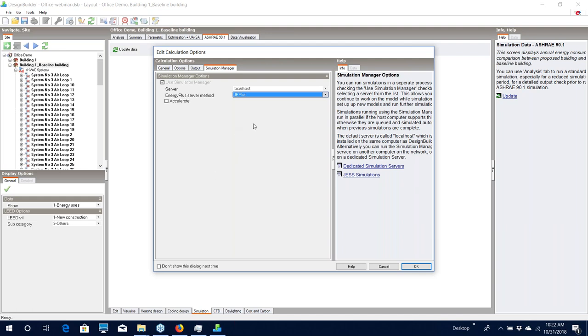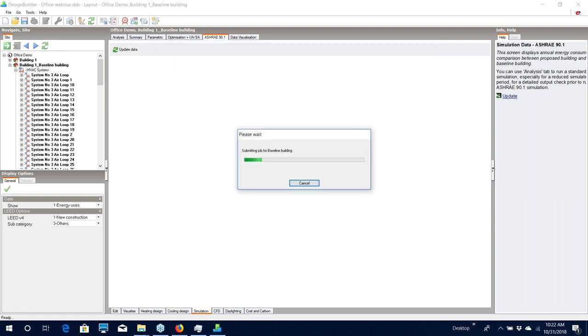The simulation manager allows multiple simulations to be run at the same time, so the different orientations can all be run simultaneously. It is also possible to run simulations in the cloud using JESS servers if you have an account. A better workflow would be to start on the analysis page and do the simulation for just one base rotation to check for errors and correctness — those are much easier to see with a single run. When doing the 90.1 with the baseline, it will run all four orientations and then average those results for display, making errors harder to spot.